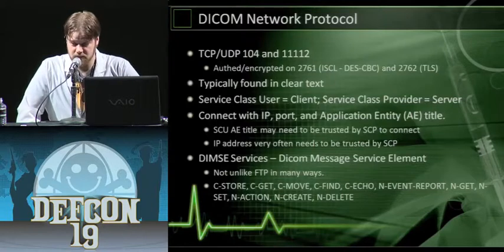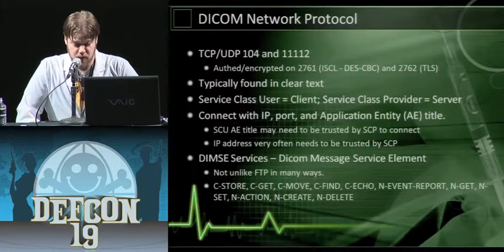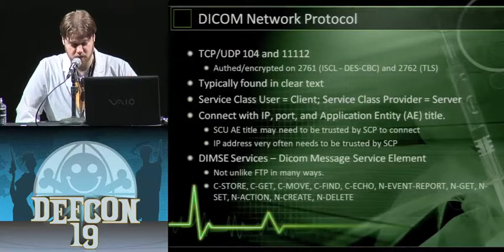To make a connection successfully to a DICOM server, you just need the IP, port, and the AE, or application entity title, which is a unique string, often the host name of the system. Now, the server usually requires that you know its AE title in order to connect - that's an almost always thing. Sometimes it will also verify the client's AE title and make sure it's on a list, and this is sometimes restricted by IP address. But those are your only protections here, so no real authentication.